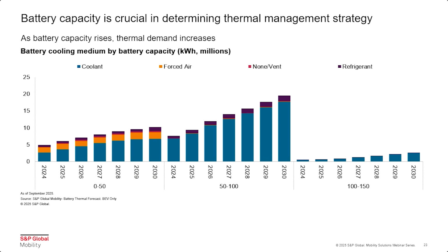Interestingly, within the 50 to 100 kilowatt hour capacity band, we also notice the use of refrigerant. As I mentioned before, this is thanks to a few OEMs like BYD who have been using refrigerant simply because of the system simplicity. Additionally, with no need for a water pump, refrigerant systems are lighter and safer, especially since the refrigerants are non-conductive. They're also theoretically more efficient because they allow for direct cooling without the need for an intermediate chiller.